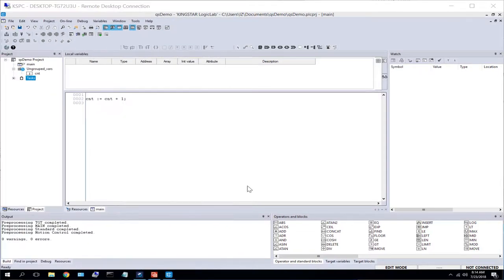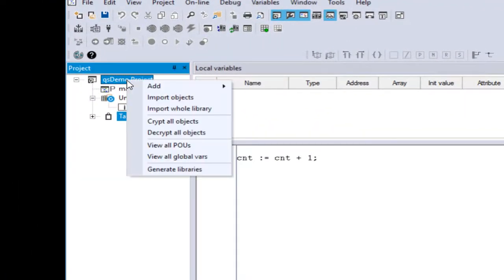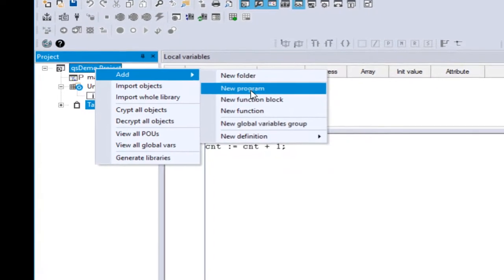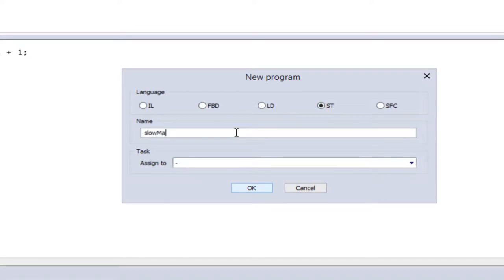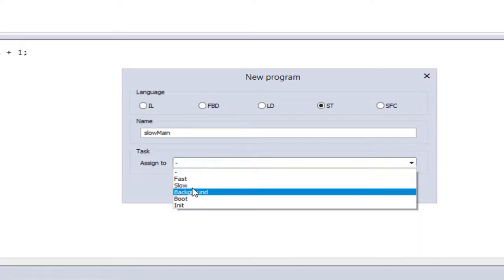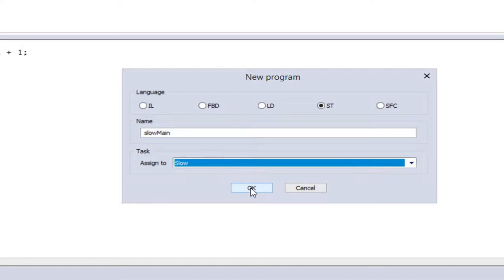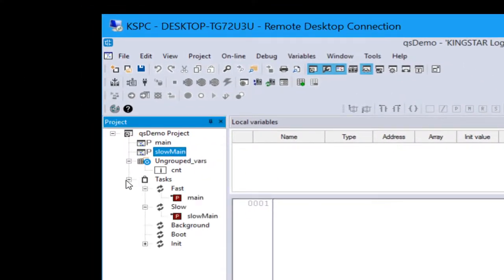To demonstrate how easy it is to work with programs and variables, let's create a new program that we're going to put in the slow task. And we'll call it slow main. So let's right click on the demo project, you get a context menu and add, and right here we'll select new program. And from there we get the pop-up dialog box and we're going to create an ST program. We're going to call it slow main, just to keep it easy. And in this case, we're going to actually select the slow task to assign it to. So by doing this, it's going to create the program for us and it's going to automatically assign it to the slow task as we can see down here under the task list.